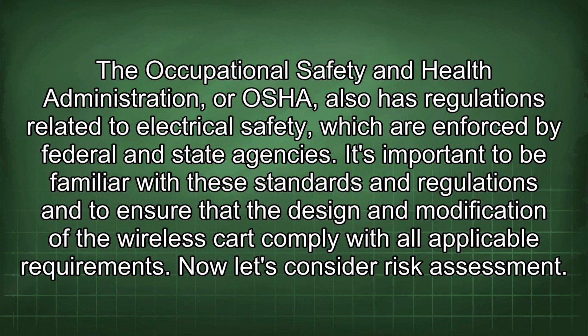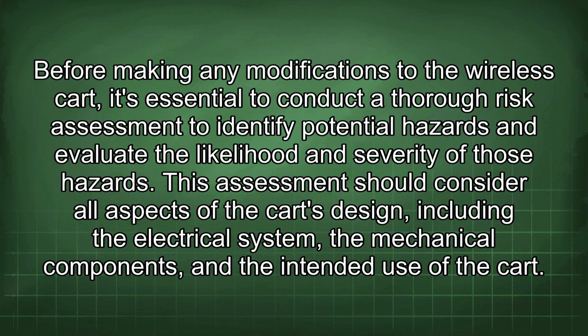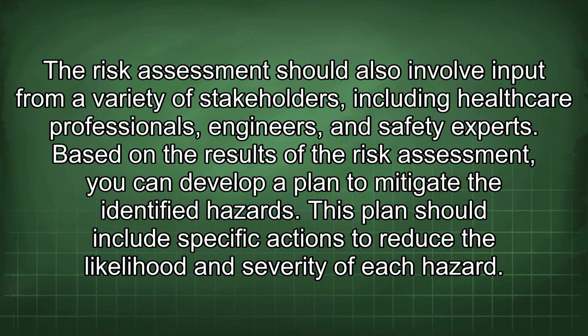Now let's consider risk assessment. Before making any modifications to the wireless cart, it's essential to conduct a thorough risk assessment to identify potential hazards and evaluate the likelihood and severity of those hazards. This assessment should consider all aspects of the cart's design, including the electrical system, the mechanical components, and the intended use of the cart. The risk assessment should also involve input from a variety of stakeholders, including healthcare professionals, engineers, and safety experts. Based on the results of the risk assessment, you can develop a plan to mitigate the identified hazards. This plan should include specific actions to reduce the likelihood and severity of each hazard.